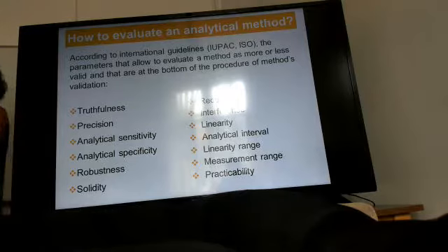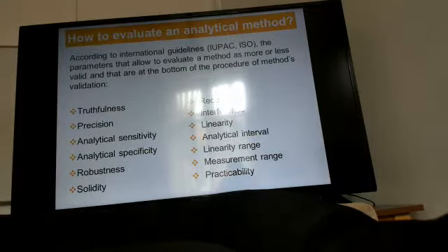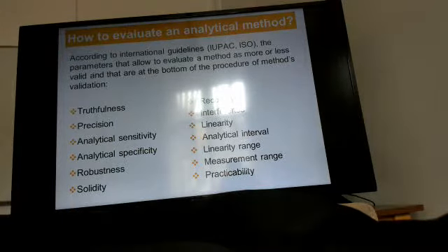And at the end of each day, in addition to the calibration in the morning, you have the statistics of the work. So if you made 1,000 evaluations of the glucose, you can see all the values. And if you see that in that day you have a lot of highest values that are strange, you can go back and verify if something was wrong.